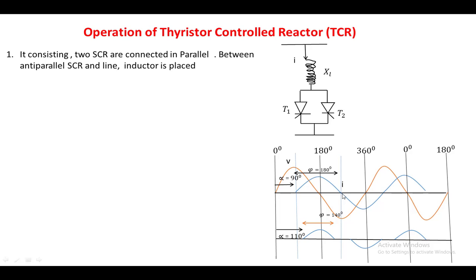T1 conducts until the current reaches its maximum and returns to zero, at which point T1 turns off. At the same instant, the triggering voltage is applied to T2, so negative current passes through the reactor. This current is purely reactive because it lags the voltage by 90 degrees.